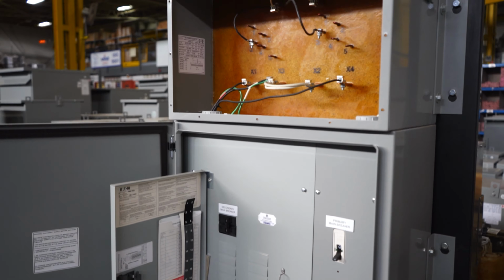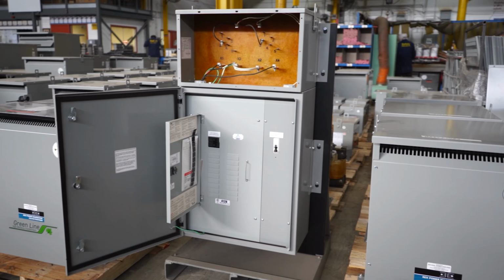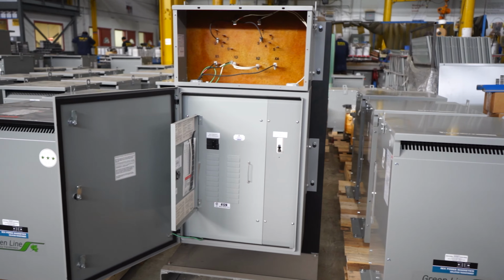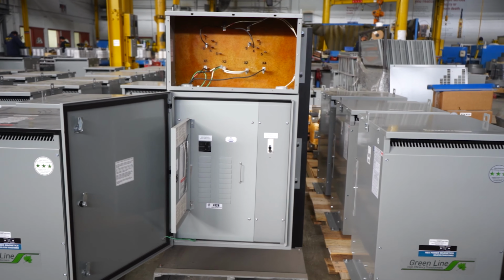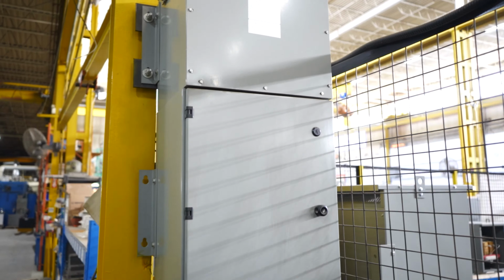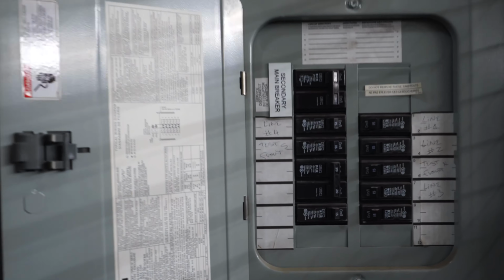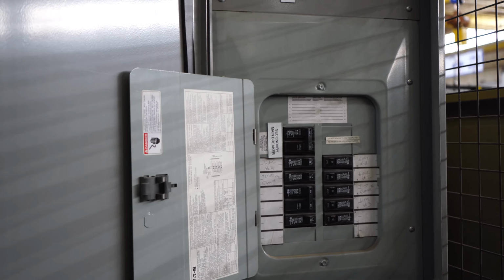The assembly includes a dedicated top section for the transformer and a panel board section underneath for the breaker and load center. All live parts are enclosed for personnel safety, and the padlockable hinged cover for the panel board section ensures that only authorized individuals can access the feeder breakers.